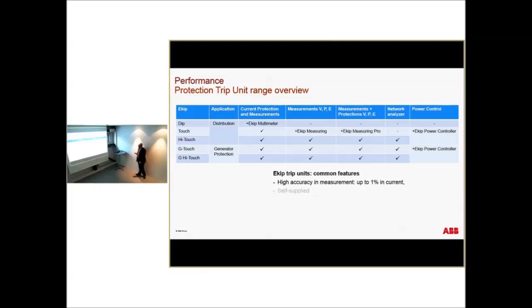In common, we already have high performance because we have high accuracy, which is 1% on current, and it is self-supplied. Reliability: we discussed before the watchdog and data logger, with a data permanent storage function. We have an internal battery. I'll show you before. In case you don't have the external TT, the external battery, in case you lose the power and everything, you again have the possibility to see through an internal battery. So it's redundant. You have three possibilities. If one fails, you have a second one, and now you have a third one. The last one is a battery.